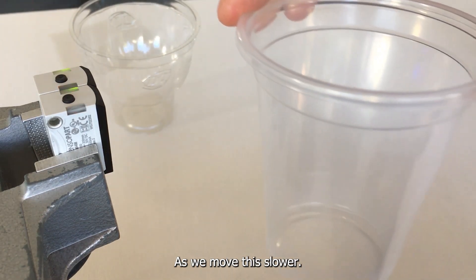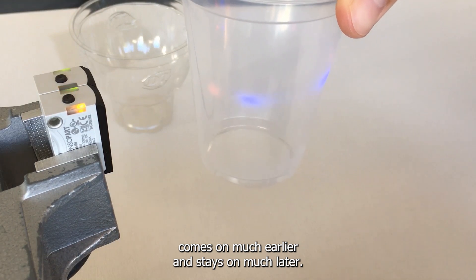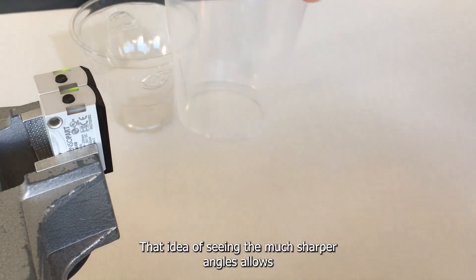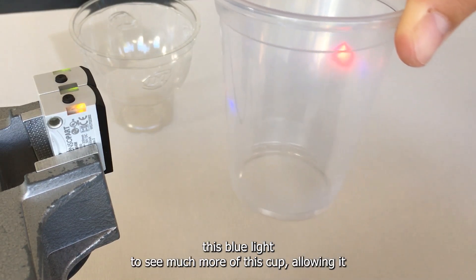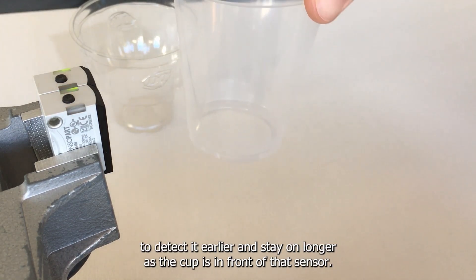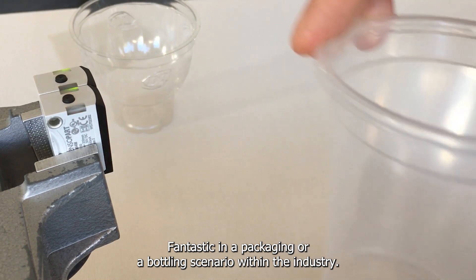As we move this slower we can actually see that the blue light comes on much earlier and stays on much later. That idea of seeing much sharper angles allows this blue light to see much more of this cup, allowing it to detect it earlier and stay on longer as the cup's in front of that sensor. Fantastic in a packaging or bottling scenario within the industry.